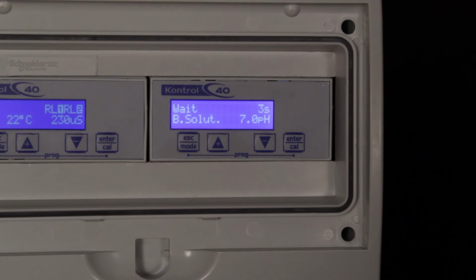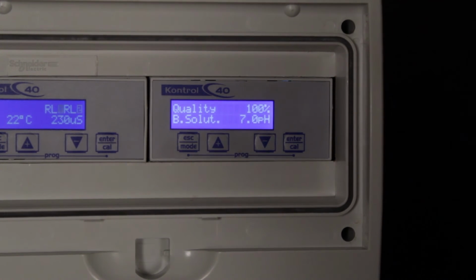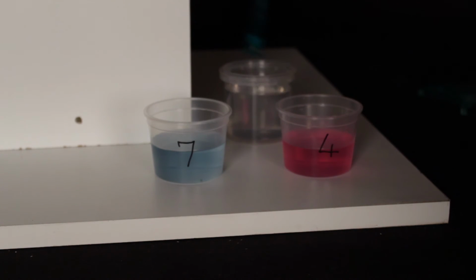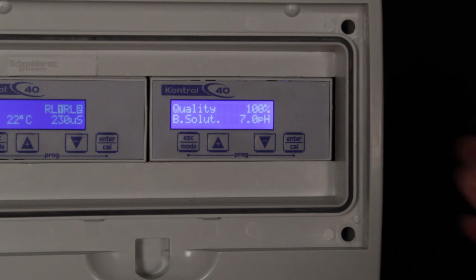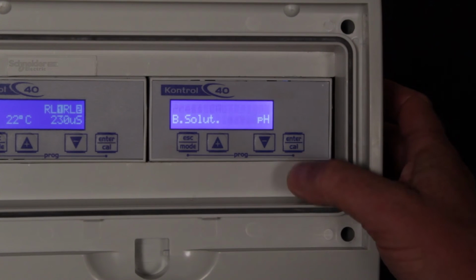One important note: once the controller has counted down to 0, it will indicate the percentage value on the screen. This indicates the quality of the probe. In this case, at a 7 pH buffer, it's at 100%. Now rinse the probe in water and insert it into the 4 pH buffer. Press enter and the controller will recognize that the buffer has changed.